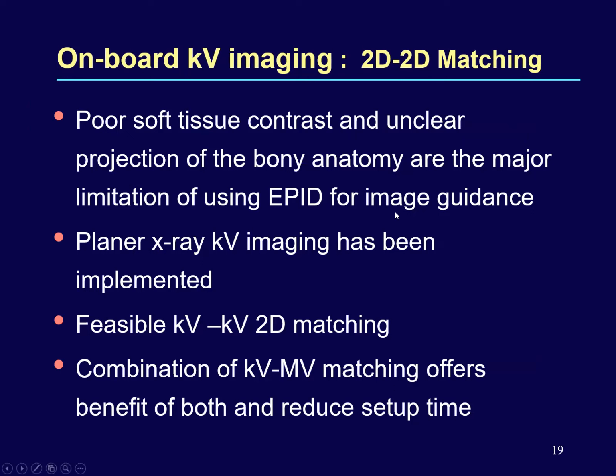So having both MV and kV, one can do either a kV-kV 2D match, or, in order to reduce the treatment setup time, one could do a kV-MV match also. And nowadays with the TrueBeam machines, even the MV images are so good and reasonable for matching.